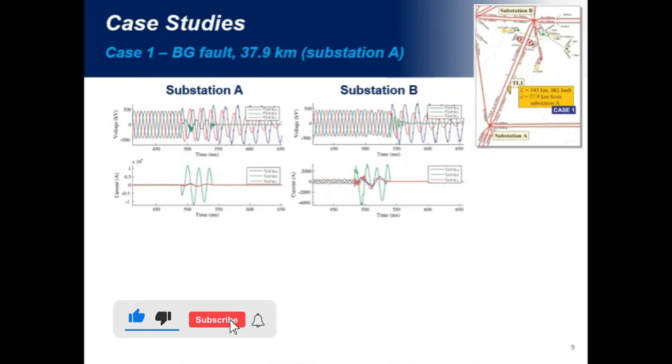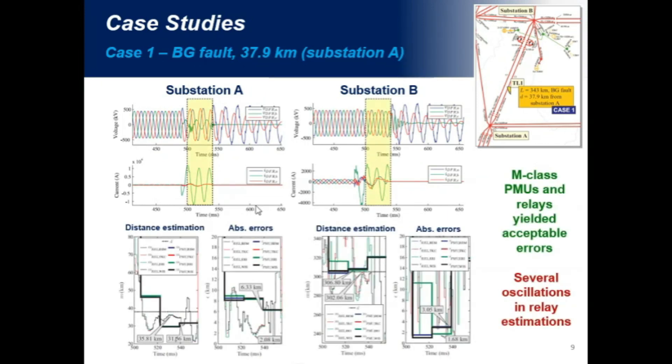In case one, these are the voltage and current waveforms. So, analyzing the fault periods, we apply fault location. Here, this line is the reference line, which represents the actual fault location found by line inspection crews. And we can see here that the fault location from relays and PMU were very close to the real one. And here, we show the absolute errors calculated from substation A. We can see here that the errors did not exceed for PMUs something like six kilometers, approximately. And using relays, it converted to errors of about two kilometers.